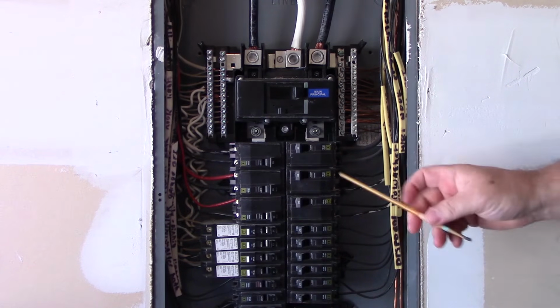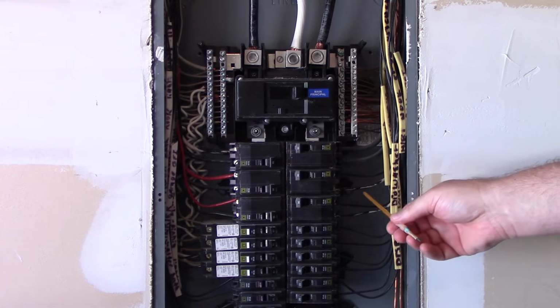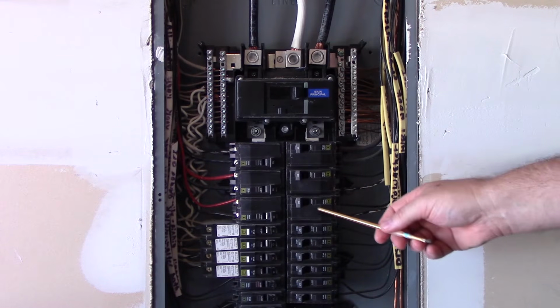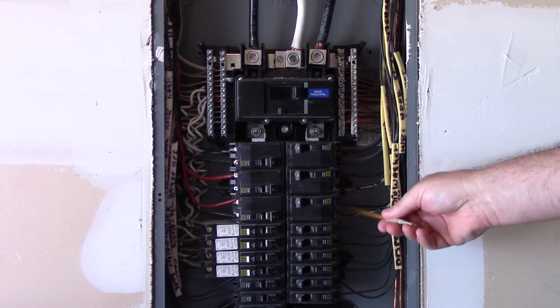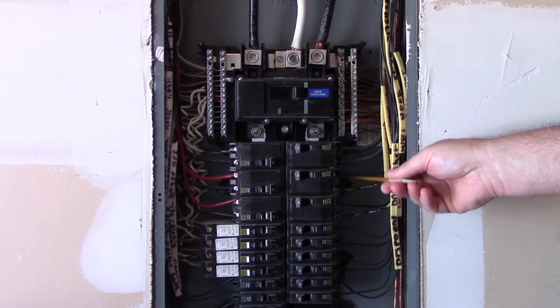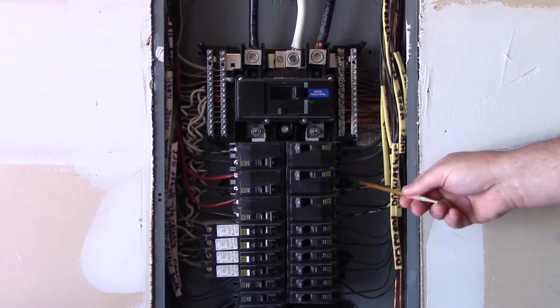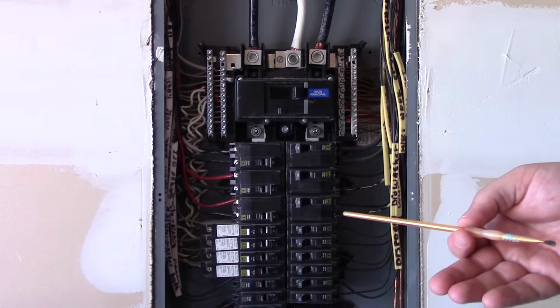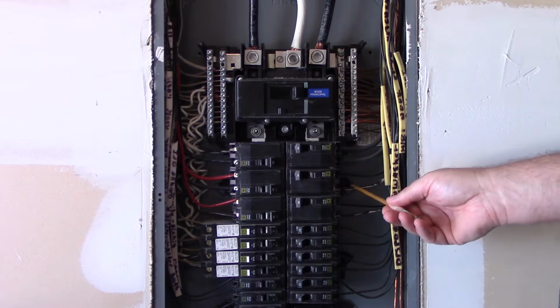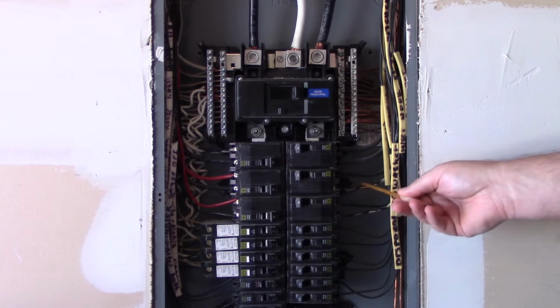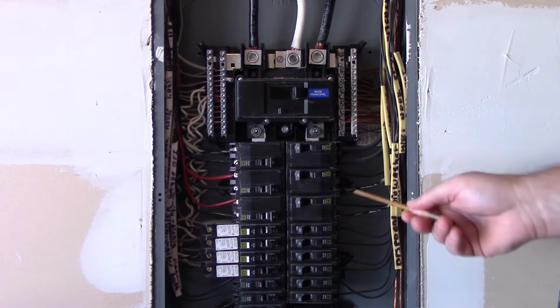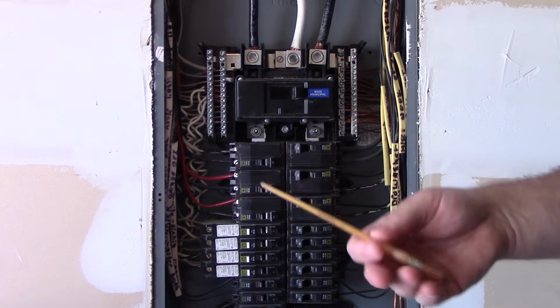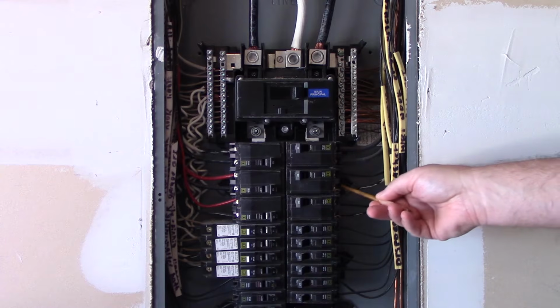All right, the other thing you'll notice in here is these conductors. This is a non-metallic sheath cable. This happens to be a 30 amp, so I know these are 10 conductors. I can tell by the size. In a non-metallic sheath cable, typically you're going to have a black and a white. The code requires that they re-identify the white in a cable for use as an ungrounded conductor, and that's acceptable. But here, they did just a Sharpie on it.